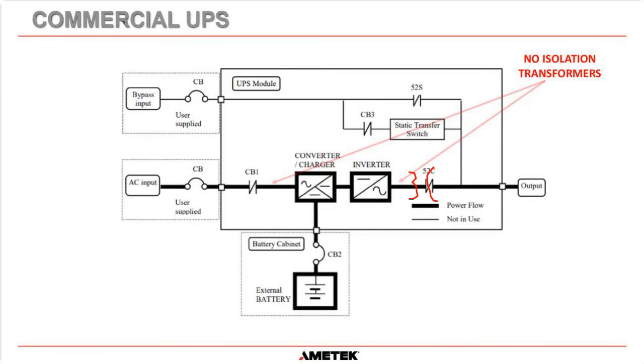If you had a fault in here and DC shorted through this way, without a transformer, that DC could propagate onto the output circuits and cause damage or issues. But with a transformer there, it can't. The DC will not flow through a transformer, and it prevents the DC propagating onto the output if there's a fault.